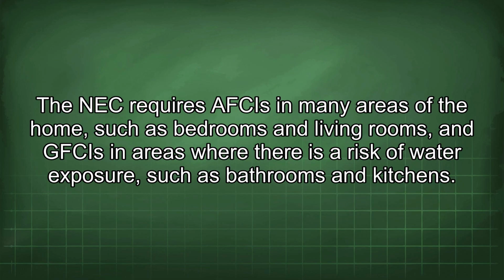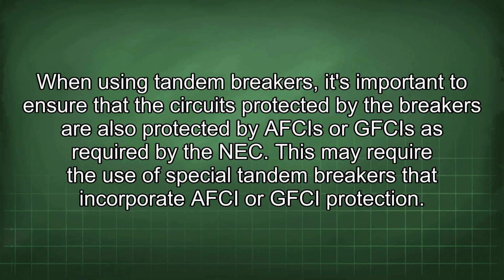The NEC requires AFCIs in many areas of the home, such as bedrooms and living rooms, and GFCIs in areas where there is a risk of water exposure, such as bathrooms and kitchens. When using tandem breakers, it's important to ensure that the circuits protected by the breakers are also protected by AFCIs or GFCIs as required by the NEC. This may require the use of special tandem breakers that incorporate AFCI or GFCI protection.